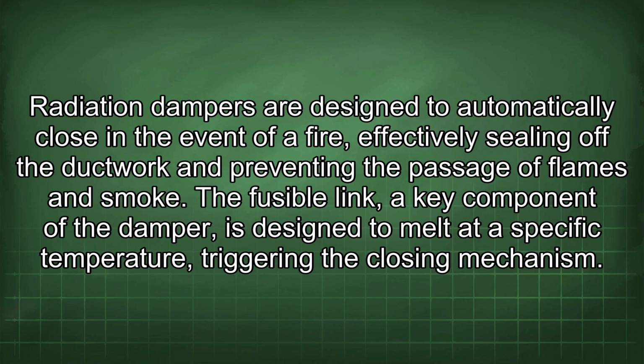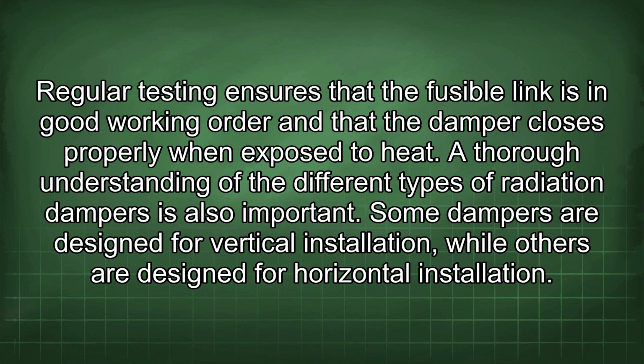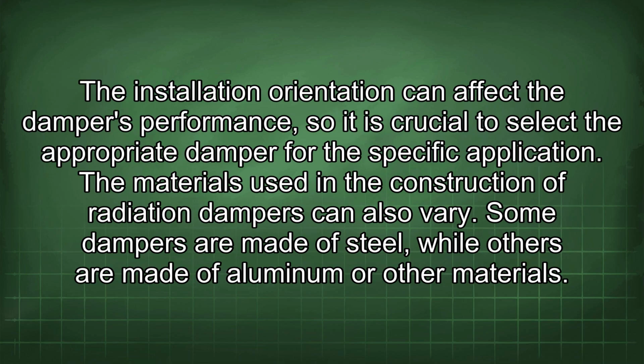The fusible link, a key component of the damper, is designed to melt at a specific temperature, triggering the closing mechanism. Regular testing ensures that the fusible link is in good working order and that the damper closes properly when exposed to heat. A thorough understanding of the different types of radiation dampers is also important. Some dampers are designed for vertical installation, while others are designed for horizontal installation. The installation orientation can affect the damper's performance, so it is crucial to select the appropriate damper for the specific application.